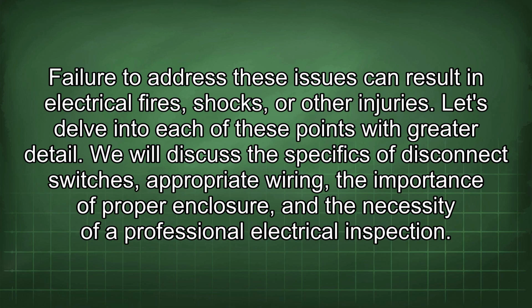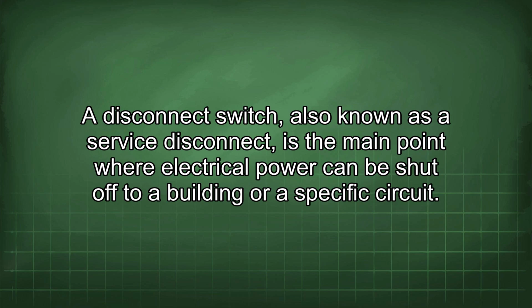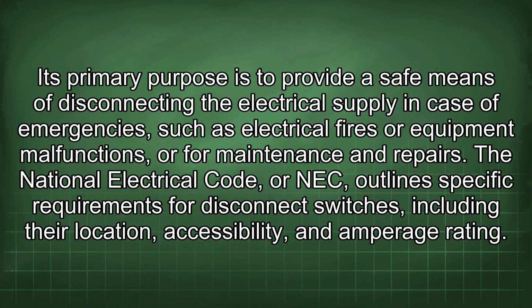Let's delve into each of these points with greater detail. We will discuss the specifics of disconnect switches, appropriate wiring, the importance of proper enclosure, and the necessity of a professional electrical inspection. A disconnect switch, also known as a service disconnect, is the main point where electrical power can be shut off to a building or a specific circuit. Its primary purpose is to provide a safe means of disconnecting the electrical supply in case of emergencies, such as electrical fires or equipment malfunctions, or for maintenance and repairs.